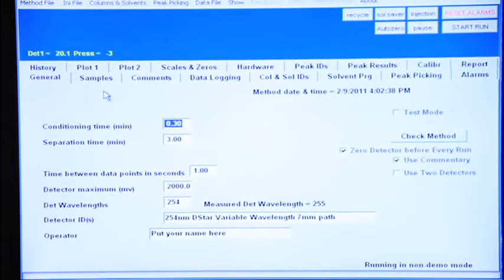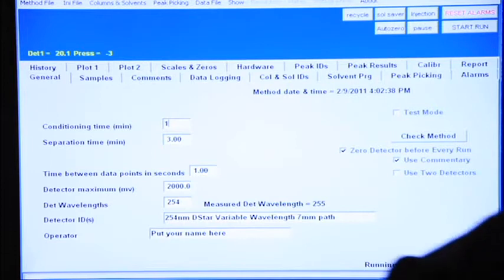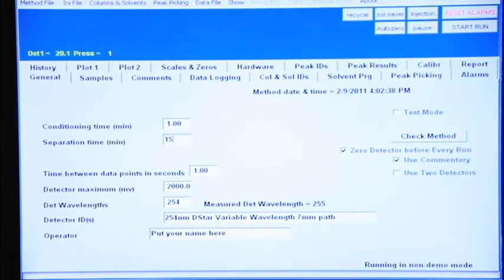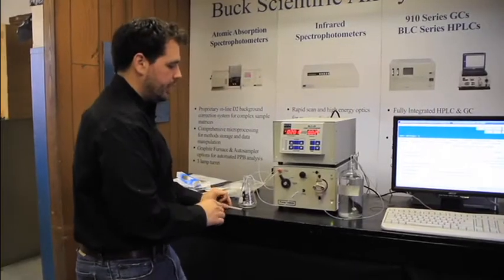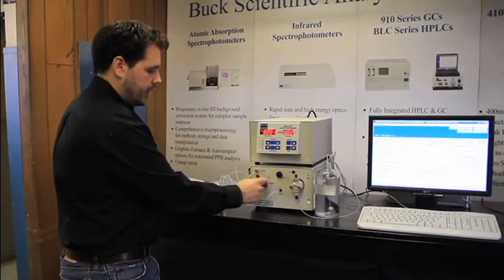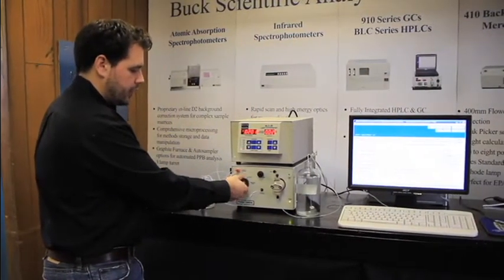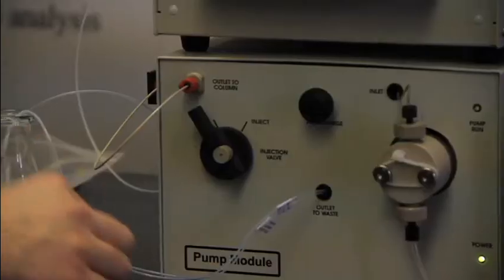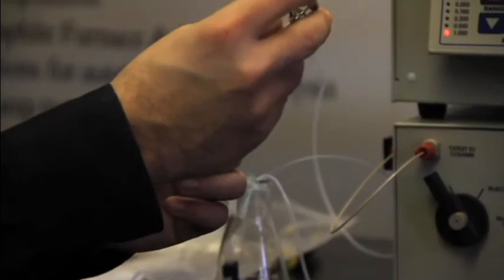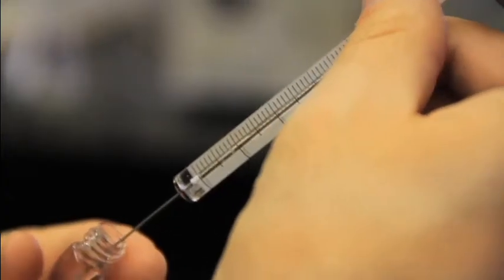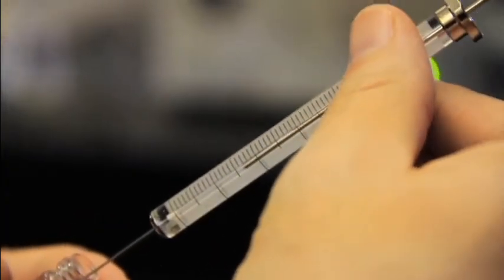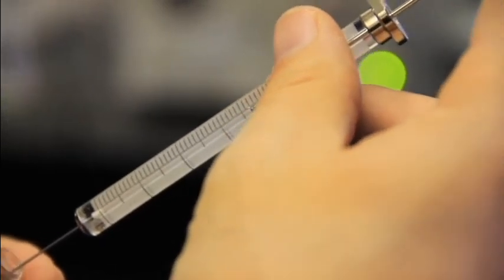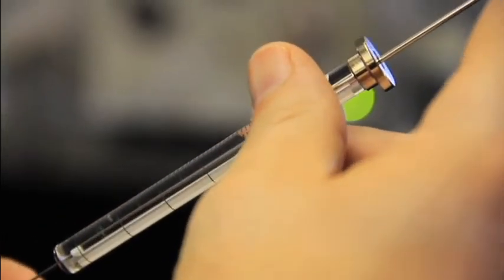I'm going to put a conditioning time of 1 minute and a separation time of 15. When you're ready to load the sample, make sure that the valve is turned to the load position and not inject. And with the 100 microliter flat-tipped syringe, you're going to draw approximately 100 microliters of sample. Obtain about 100 microliters of sample in the syringe, being careful to avoid getting bubbles in the syringe.